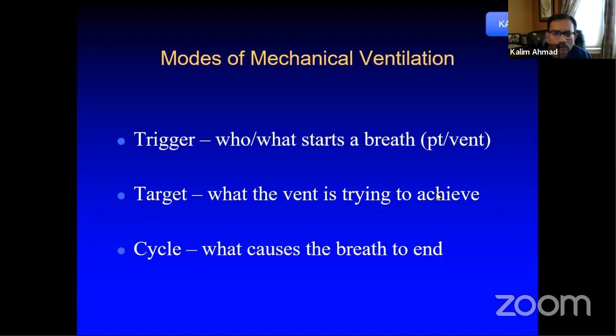In an assist control mode of ventilation, the machine will trigger the breathing. The machine is dialed in a way that, with a set time, it is going to provide a breath. What starts the breath? How is the machine going to sense? Patient or vent? Either the patient is going to initiate or the machine is going to initiate that process. And then we set the trigger by dialing in either some negative pressure or flow pattern, and we'll talk about that in future. But basically, this is what initiates the breath.